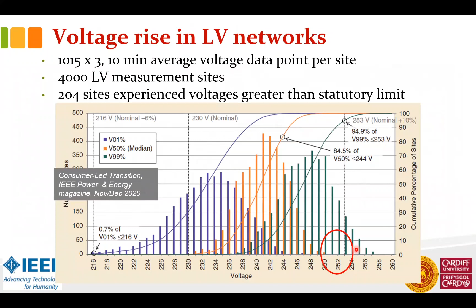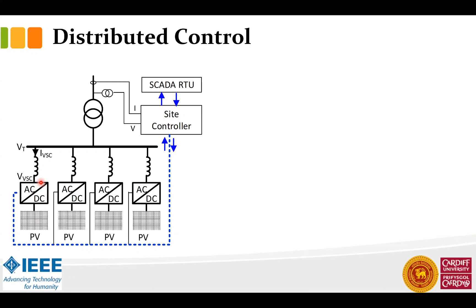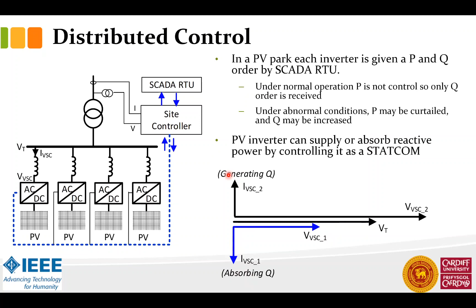Now, one thing you could do, and this is slowly coming into what we call smart grid approaches, is that your solar inverters can be asked to supply reactive power to the grid. You can either supply reactive power or absorb reactive power. These solar inverters will obviously send active power, but they can absorb or generate reactive power. If the voltage goes up, you absorb reactive power and reduce the voltage. This is called STATCOM operation, static compensator.